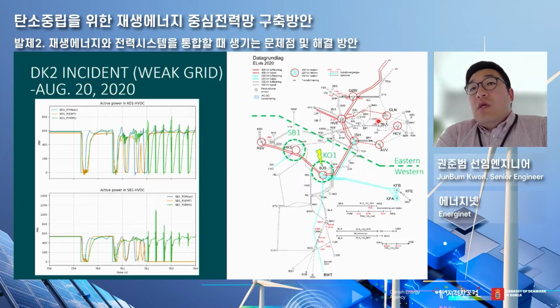The models we received from vendors and developers were quite simplified, but what we need is an EMT model with full trigger function. When there's an accident, we can compare this data: the blue line is the actual measured data, orange is EMT, and green is RMS. The RMS model, we could not use for simulating the accident.